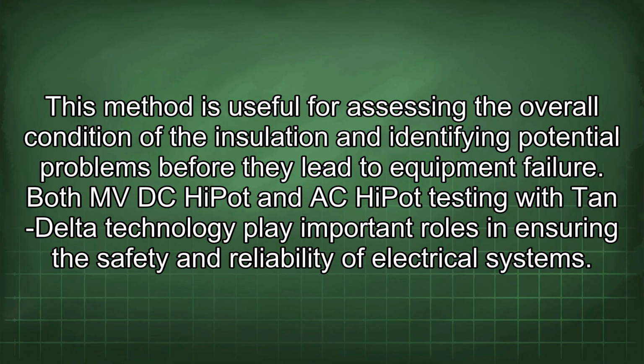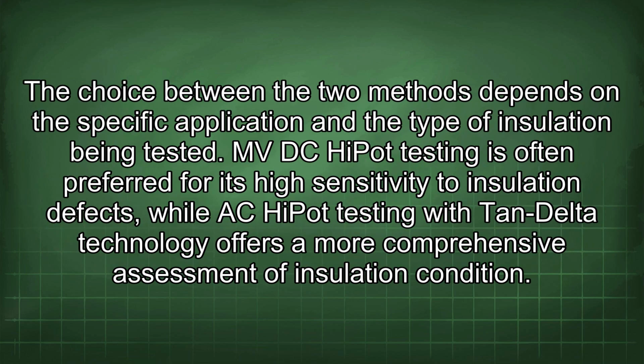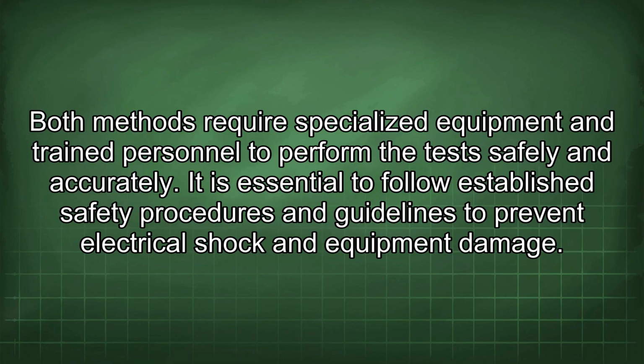to equipment failure. Both MVDC HiPot and AC HiPot testing with tan delta technology play important roles in ensuring the safety and reliability of electrical systems. The choice between the two methods depends on the specific application and the type of insulation being tested. MVDC HiPot testing is often preferred for its high sensitivity to insulation defects, while AC HiPot testing with tan delta technology offers a more comprehensive assessment of insulation condition. Both methods require specialized equipment and trained personnel to perform the test safely and accurately. It is essential to follow established safety procedures and guidelines to prevent electrical shock and equipment damage.